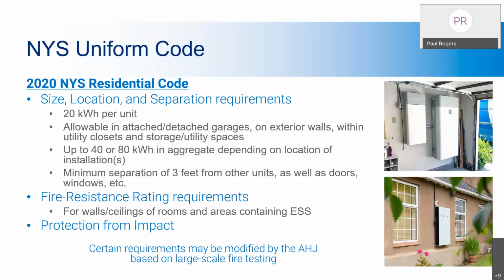Certain requirements may be modified by the AHJ based on large-scale fire testing. So if someone did their homework, and we'll talk even outside of lithium ion, maybe it's a different chemistry, and they did some large-scale fire testing that really shows there are no concerns when these things fail, whether they don't go on fire, or there is no fire contained, or there's no explosion or anything like that, then why should they be held to the same requirements as everyone else? They realize that's an issue. So the code committee said, okay, we're going to give some authority to the authority having jurisdiction, which is your local code enforcer, the one who approves these installations. They said if they can do some large-scale fire testing and show that it is safe, then that local code enforcer can actually allow these installations, or could modify some of the things required in the code itself. You can go to the next slide, please.